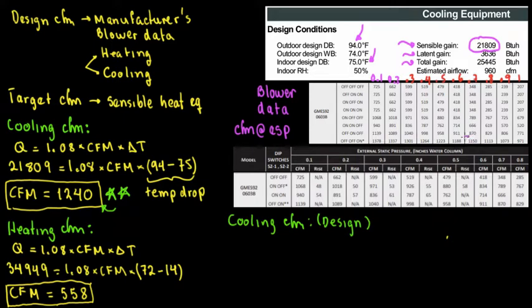At 0.7 inches of water column, the maximum we can obtain is 1,150 CFM, so there might be issues — it's not safe. We need 1,240 CFM, plus the installation is not 100% perfect. We also need to consider that homeowners sometimes forget to change the air filter, which increases resistance and decreases CFM. We need to lower the resistance, which means targeting 0.5 inches of water column.